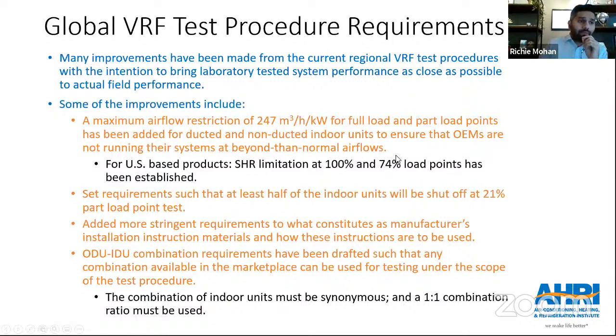But again, for regions which are outside of US and Canada, I think the intention is to tackle the airflow side of things with an airflow limitation, which is 247 cubic meters per hour per kilowatt. Now, beyond that, we've also added a requirement on the part load side where, let's say for your lowest part load condition, which is 21%, you need to have at least half of the indoor units be shut off.